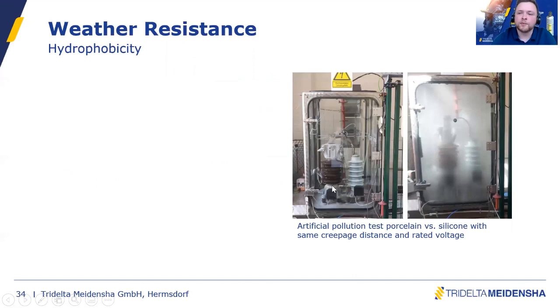To make my arguments even stronger, I show you a test we have performed in the past years, an artificial pollution test with very harsh requirements we know from the coastal area and the desert. So much salt fog, high humidity in morning hours, temperature, contamination, and so on and so forth. And we put two kinds of surge arrestors inside, one porcelain housed, one silicone housed surge arrestor, with almost exactly the same creepage distance and the same rated voltage. So the conditions are the same.